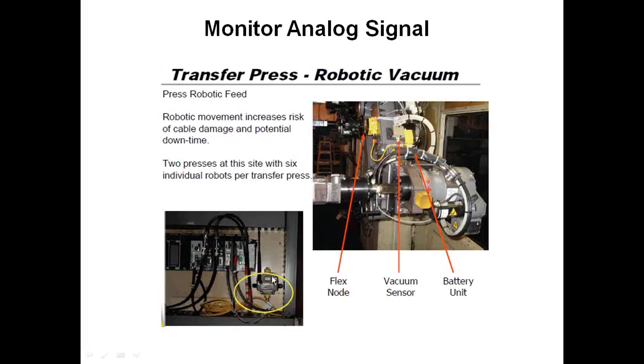One thing here to be cautious of, you'll notice the gateway got mounted inside of an electrical control box with the antenna, and it worked. But really what you're going to want to do, if you're going to mount any wireless radio inside of a metal box, is run an extension cable to a bulkhead fitting and then put the antenna on the outside of the enclosure. If it's a fiberglass enclosure, typically we're okay. That doesn't degrade the signal or the RF very much. But if it's a metal box, you really want to get this antenna outside the application.